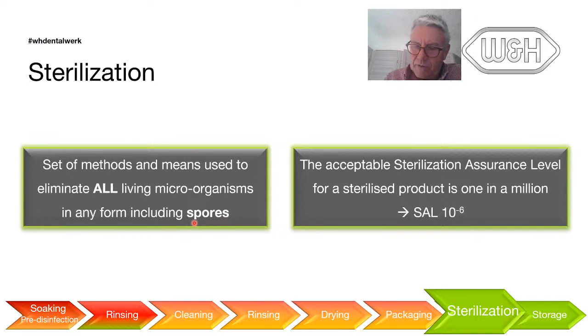What does this mean? This is the meaning of SAL 10 to the minus 6. It says sterilization or sterility assurance level of 1 in a million. So if you load your instruments and there are 1 million microorganisms, only one is allowed to survive. I know it sounds strange, but it's a fact. It's reality. It's the same in hospitals. It's never going to be zero. So this is the importance of all these first steps, especially pre-disinfection.